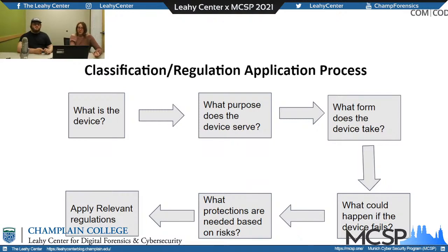So for these two things, would they still go in the same class, or do they get differentiated because one's a cybersecurity risk versus the other one's a physical risk? It depends. In the US, it's a little more device by device. The FDA has a database where you can look up different devices. If you type in pacemaker, there's a device classified as a pacemaker that's only a class 1 device, while at the same time there's one that's a class 3. So it very much depends on the device in the U.S.